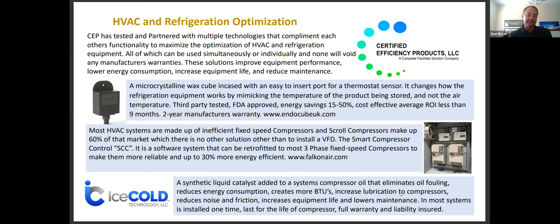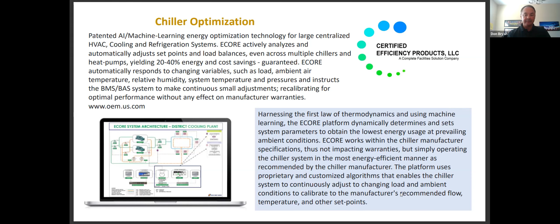And you can see energy efficiency increases anywhere from 10 to 25%. We're installing this product in grocery stores, hospitals, anybody that is a big consumer of energy from HVAC or refrigeration. IceCold is a great product that's been around for more than 20 years and is also very cost effective and non-disruptive. We have an E-Core program that works to optimize chillers, and it works with any type of BMS system that you have in place. It works in conjunction with it. This is a third-party company that we use to implement this technology, and they will do the assessment and then guarantee the savings that you're going to get before installing it. So it's a very effective technology for optimizing chiller plants.